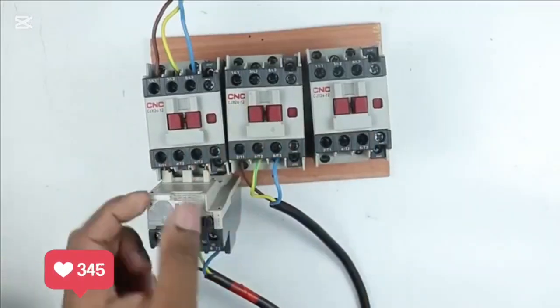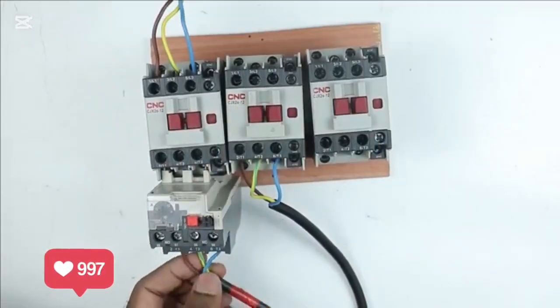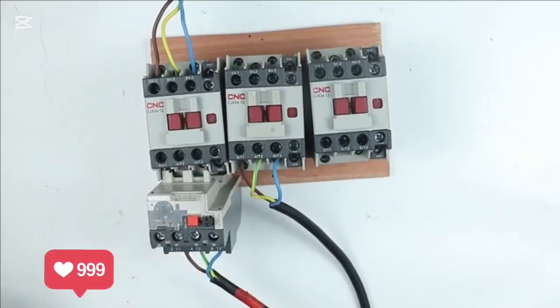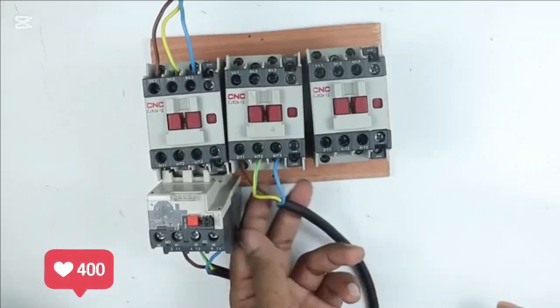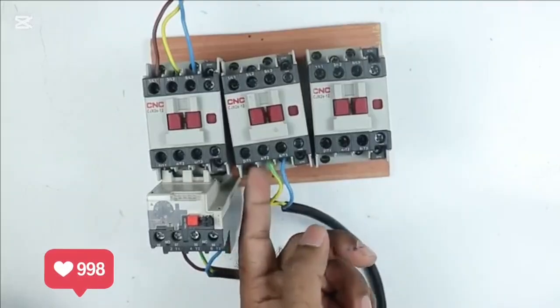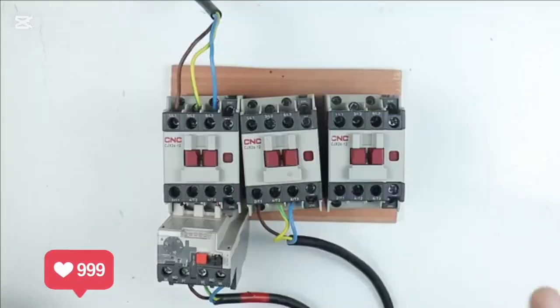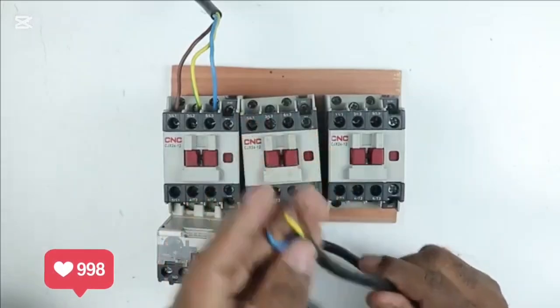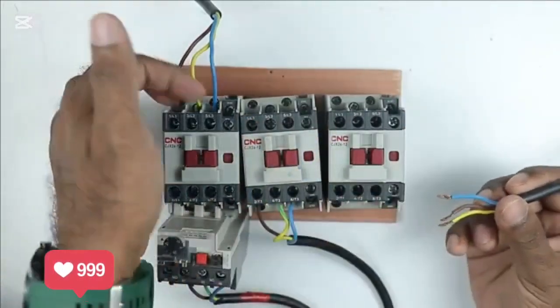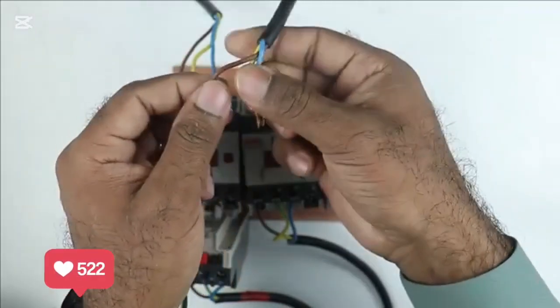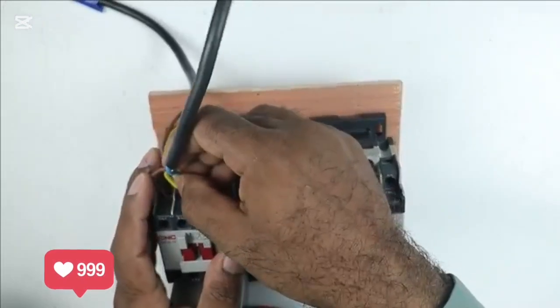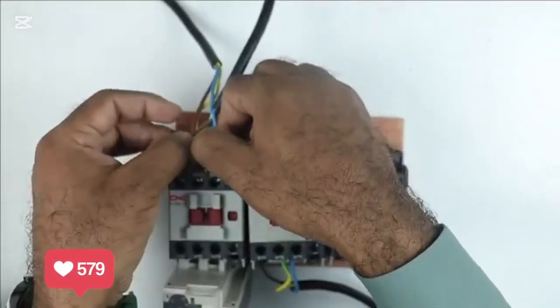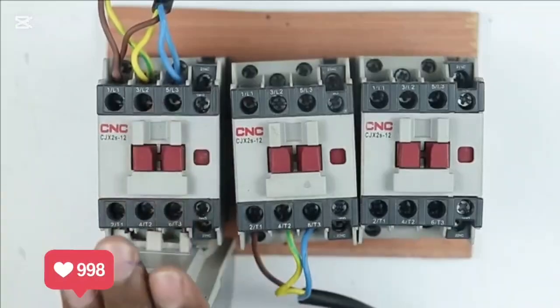Now let's come to the starter. In this starter we have, from the overload relay here, the power which is supplied from here. From now let's take R phase. So R phase power supply which is going inside the motor, in return it comes to this R wire only. The power supply in return will go to another phase power supply. To this delta contactor, for providing input power supply, take 3 wires. I have 3 wires here. Take these wires and connect with input power supply. You have to connect according to phase sequence only. It means connect red wire with the red wire, yellow wire with yellow wire, and connect blue wire with blue wire. You can see here according to sequence connection is done.